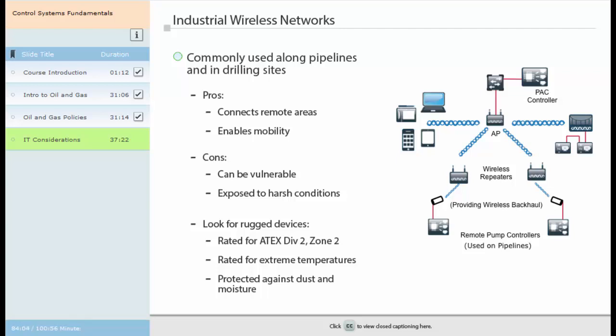When developing a wireless approach, the effects of conditions like extreme hot and cold temperatures, outdoor exposure to sun, wind and rain, and loud vibrating machinery on wireless equipment need to be taken into consideration. When selecting wireless products, look for rugged and hardened devices that are rated for harsh environments, ATEX Division 2 Zone 2, rated for extreme temperatures, protected against dust particles and moisture.